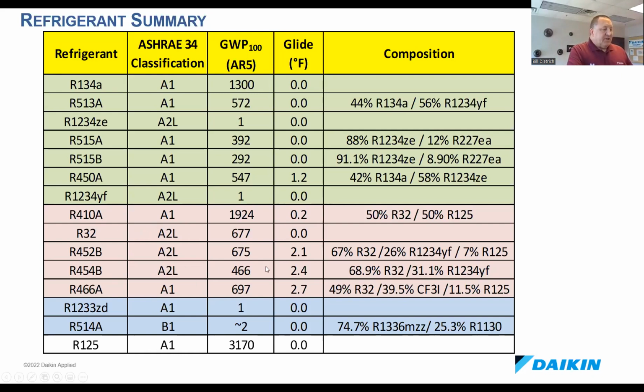But when you get to some of these other refrigerants with higher glides, they may not be suitable for use in flooded or falling film evaporators because of the potential for fractionation. You can see the low pressures, both the 1233 and the 514 are considered zero glide. The 514 is a blend, and that's what it's made up of. I put the 125 here for interest because that is 50% of what is in 410A, and with that higher GWP, that's what's driving that higher number up closer to 2000.